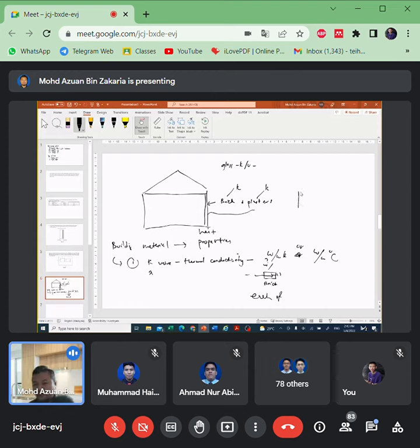All right. For example, normally we have brick and plaster, right? And plaster layer at outside. Okay, so brick, for example, 100, plaster is 25. So the brick has its K value, and then the plaster has its K value. So when combined, it will create resistance to heat. Good. Then we can call number two resistance. Okay. Thermal resistance.